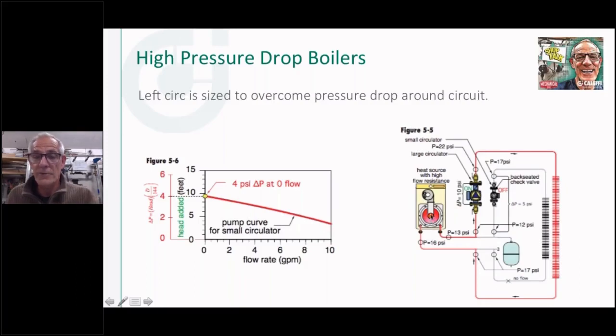And this comes right out of one of the Idronics issues. So pay attention to, hopefully you can see these clearly on your screen, all the different pressures that we have going on in this picture as we start pumping through this boiler with a single pump. We've got a high pressure drop boiler here, call it a Munchkin, whatever brand you'd like to use for that type of boiler. We've got a circulator pump. We also put in a high pressure drop distribution circuit on that, the red circuit.